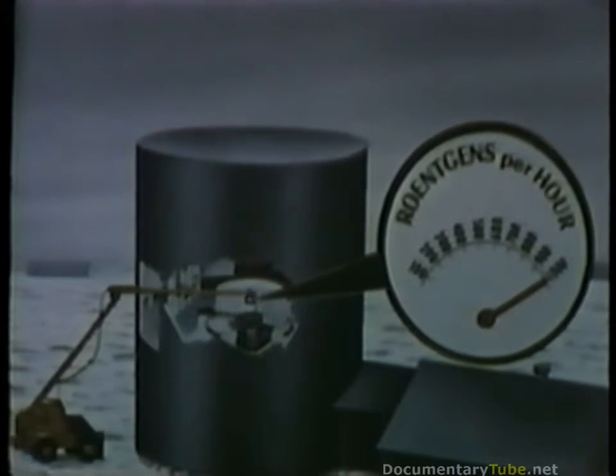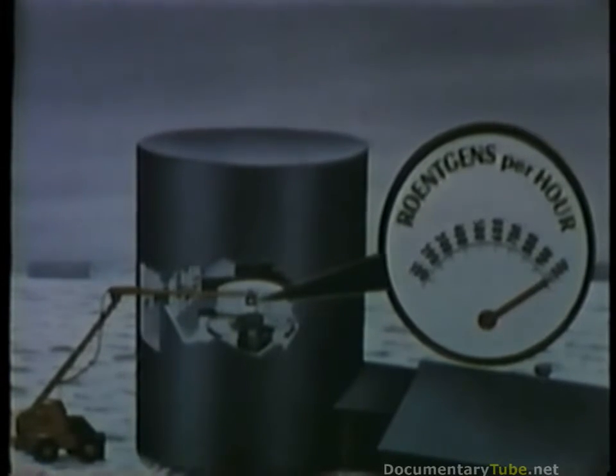First estimates of the radiation field in the reactor room were calculated to be approximately 1,000 R per hour. By late April, the radiation levels had decreased to the 200 R per hour range. Films from a pinhole camera spotted several locations and sources of high gamma radiation activity outside the reactor vessel, presumably from reactor components blown from the core by the force of the explosion. Calculations of the energy needed to cause the observed damage to the ceiling and the reactor indicate that the explosion was sufficient to create an internal pressure of at least 500 psi.